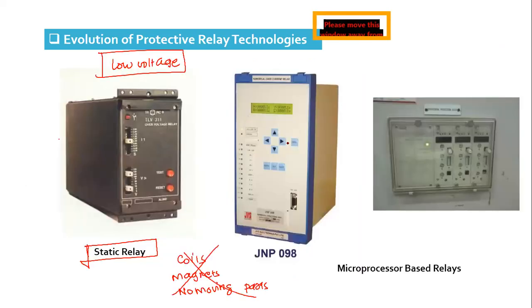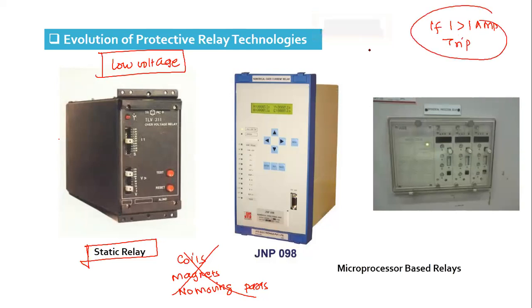The same function can be done using a microcontroller relay with an actual comparison. You studied microcontroller, so you will read the data and check if current is more than 1 ampere, and if so it trips. Same function is done, but here there is no force, torque, nothing, only comparison. It actually calculates or compares. That is the same function, but in a different way. You have a program, you read the data, and the program compares and, according to the logic, performs the task, resulting in trip or no trip. That is what is called the microcontroller based relay.